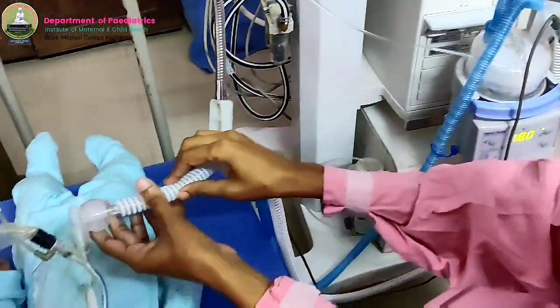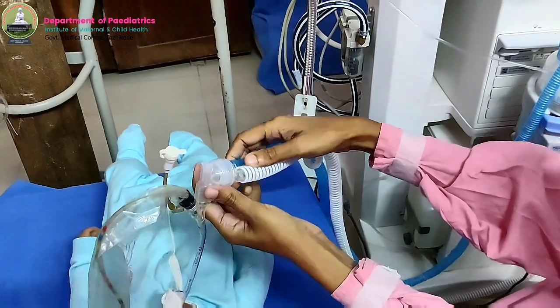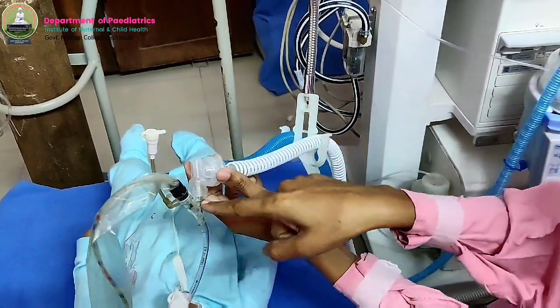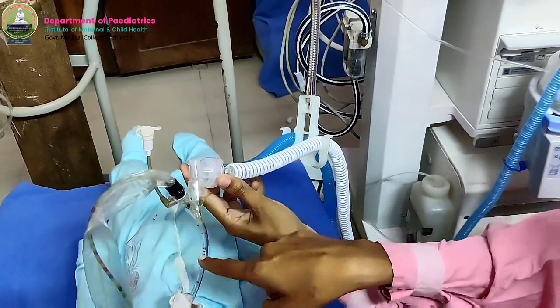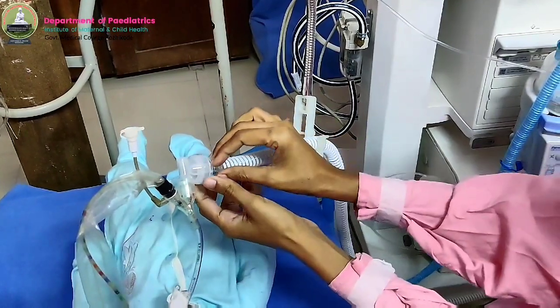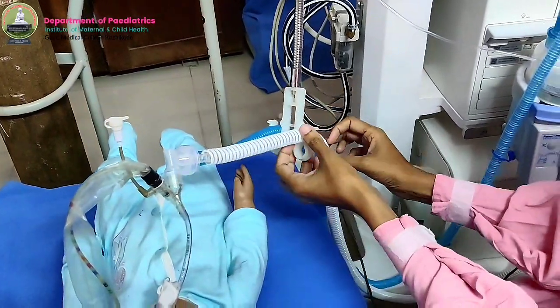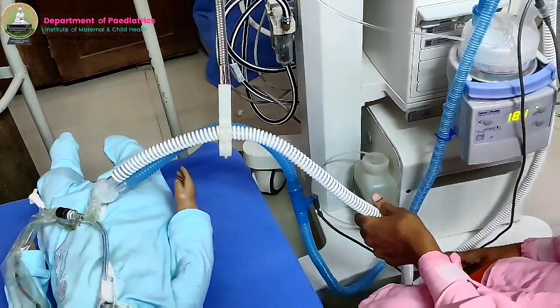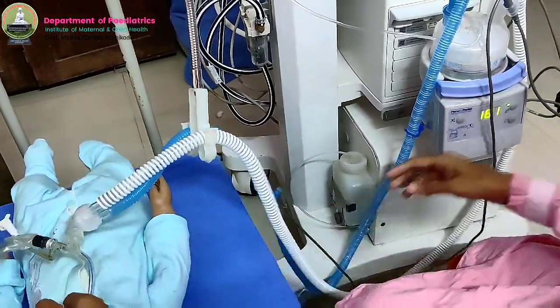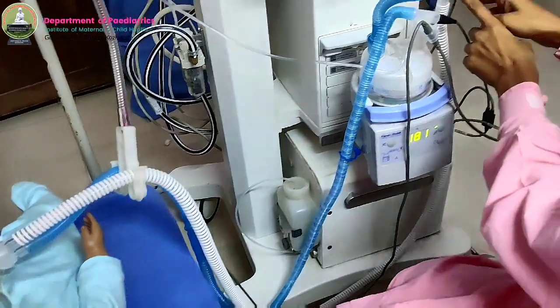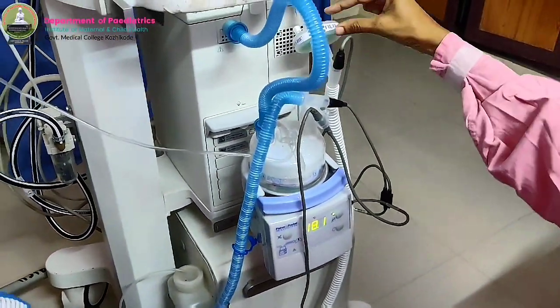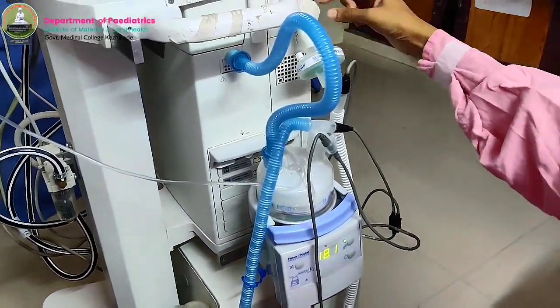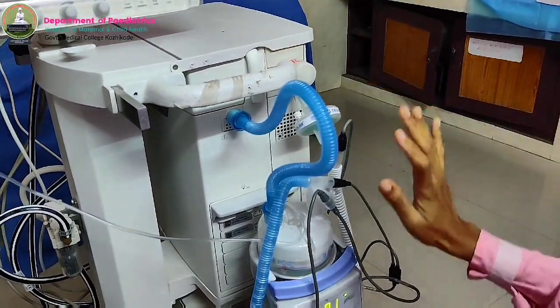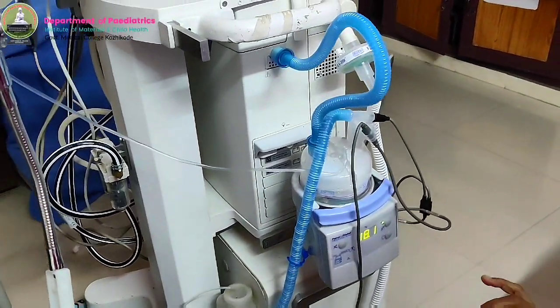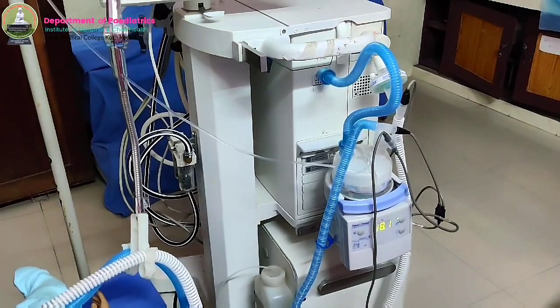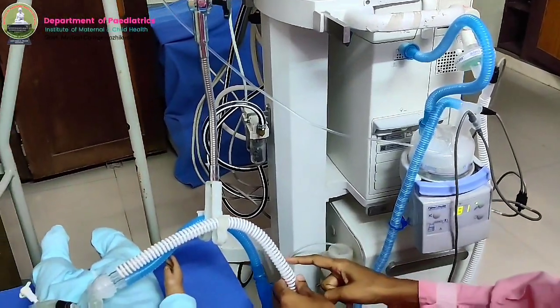Then we have a Y connector here. This is the Y connector which is connected to the closed suction device and the ET tube. From here is the expiratory limb, the white colored expiratory limb. It is a continuous one reaching the expiratory end of the Maquet ventilator. There we will connect a virus filter, and this is the expiratory cassette. So this is the circuit connection of the Maquet ventilator. Both the limbs have heated wire.